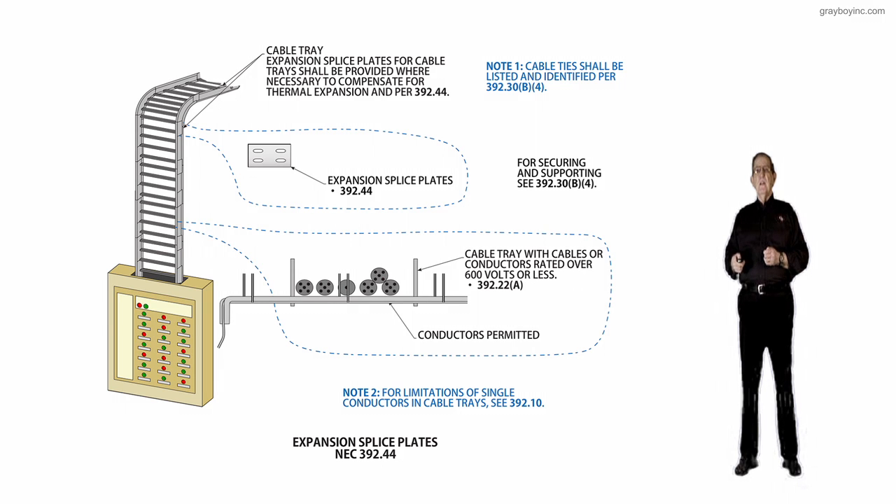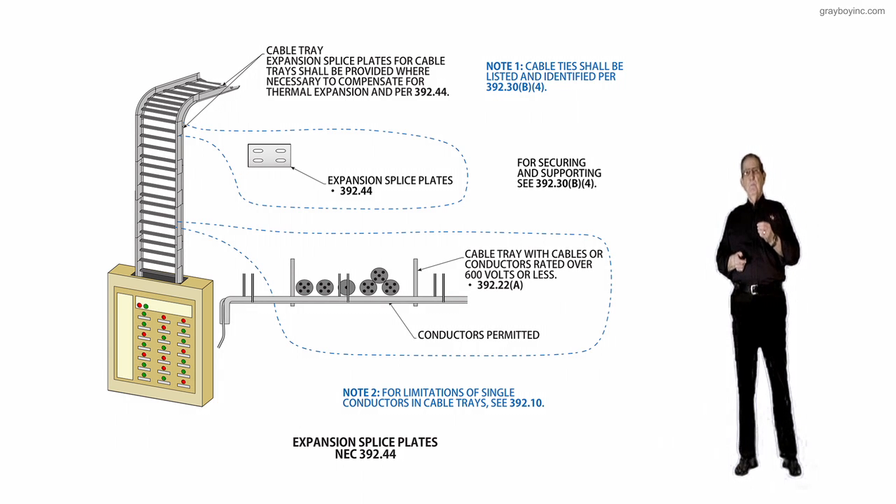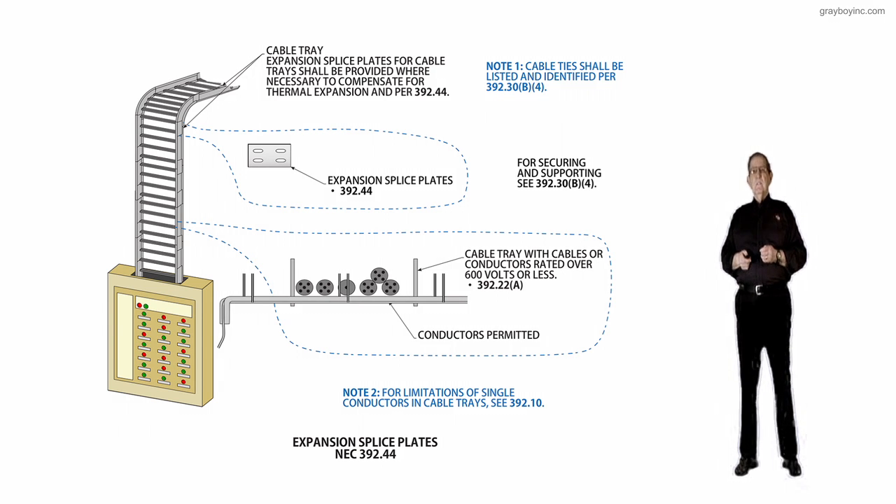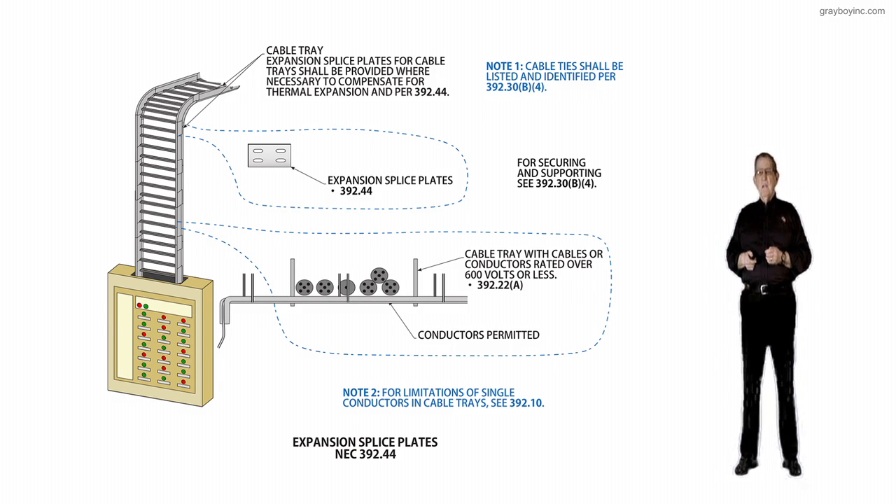Note 2, just above the caption, says for limitations of single conductors in cable trays, see 392.10 for those rules. If you're looking for individual conductors installed in cable trays for support, see 392.22.B. For multiple conductor cables, see 392.22.A.